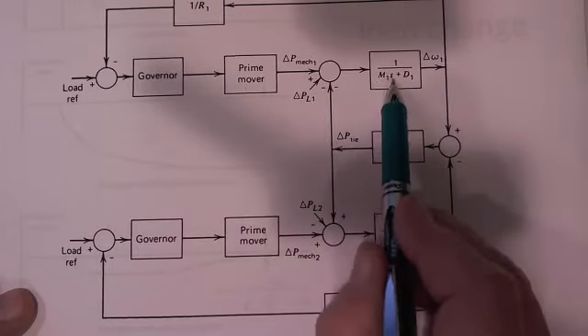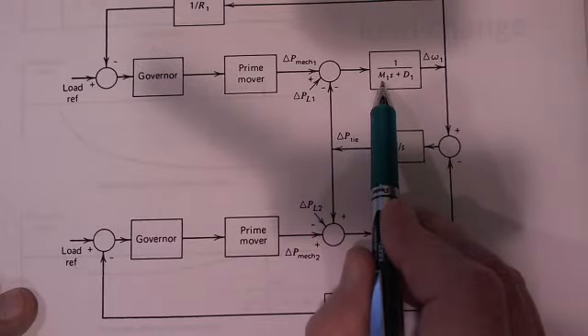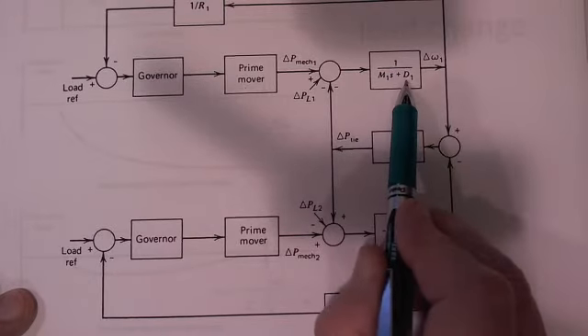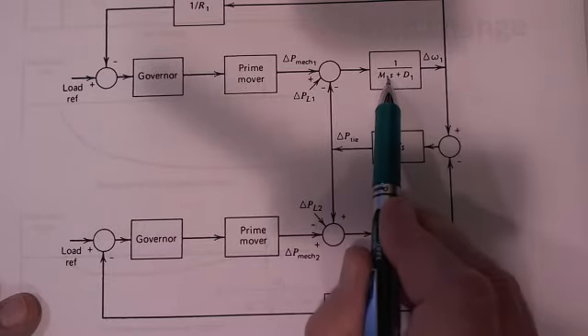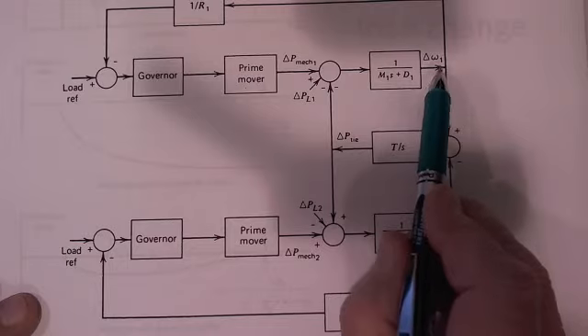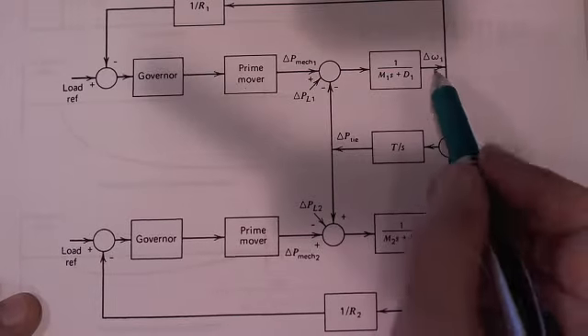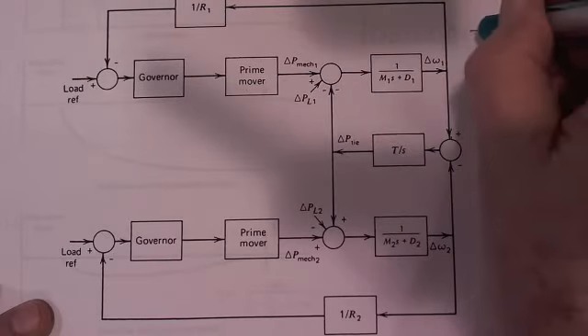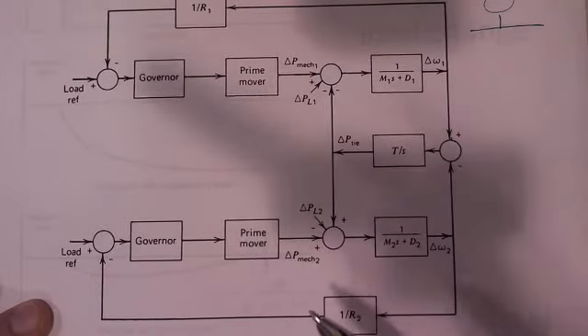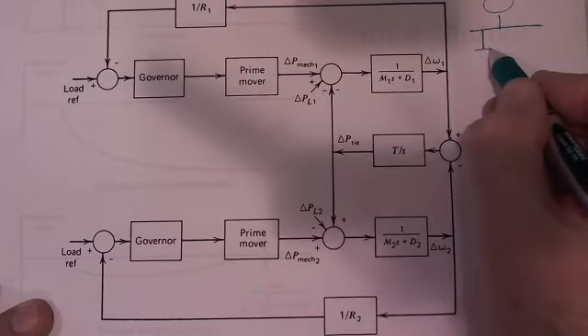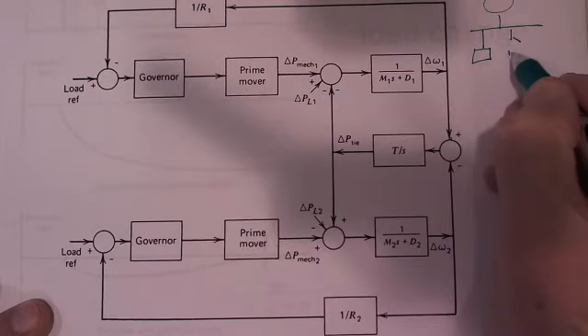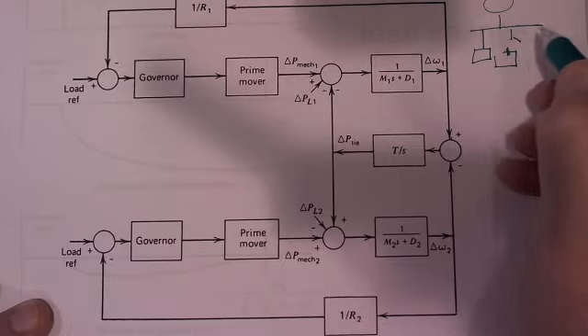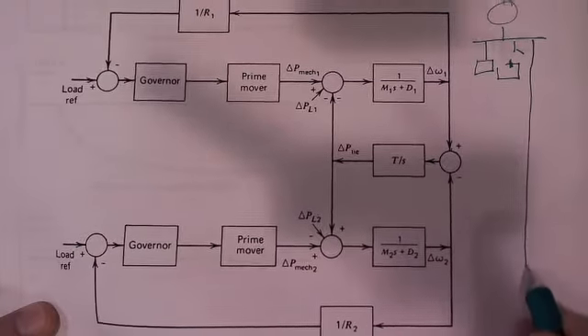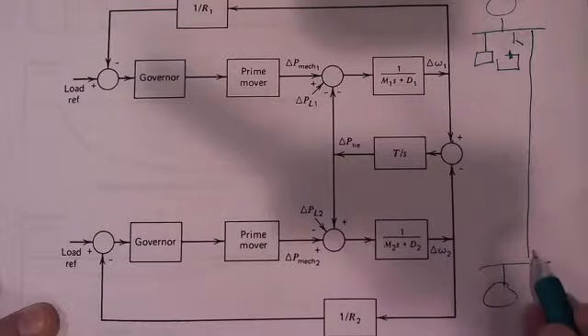This represents the 1 over Ms, which is just the mass of the rotating mass, and then there's a little load damping in here. If you put power into a rotating mass, you go 1 over s, and you get a change in speed. So this represents a generator up here, and we've got a load down here, and maybe a load with a switch. Then we've got a tie line that goes down here to another generator. This is number 1, and this is number 2.